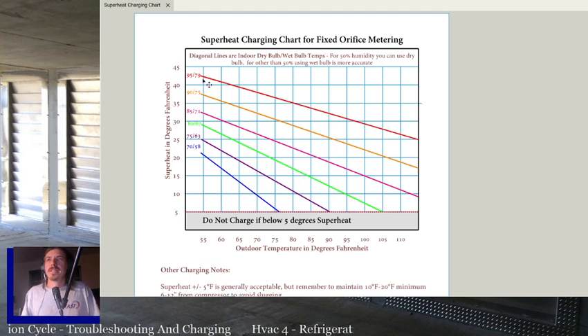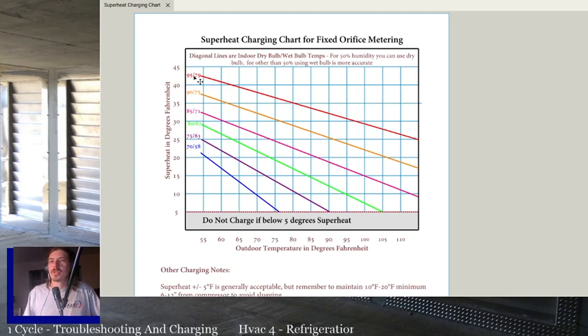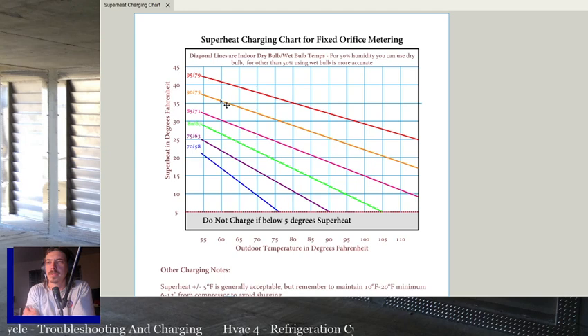It gets real crazy. You can see your superheats can get super high if it's cool outside and it's warm inside. So it's something to keep in mind. If you're servicing a system in the evening when it starts cooling off but it's still really warm in a house, then your superheat's going to be practically through the roof. So that's when a lot of overcharges happen. Even good techs sometimes will overcharge on a fixed orifice when it's cooler outside and warmer inside.